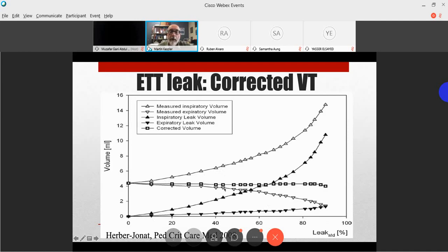Now, in this bench model, they were quite PEEP-phobic. They used a low end-expiratory pressure. If you use a higher end-expiratory pressure, the leakage during the expiratory phase, which is driven by PEEP, will be more. But even with this relatively very low PEEP, you begin to see a significant deviation from the actual set tidal volume. And so they proposed a way to calculate the actual delivered tidal volume despite a progressively larger leak around the endotracheal tube.